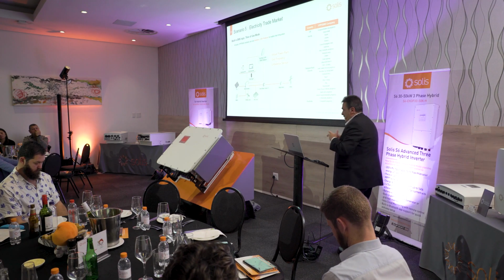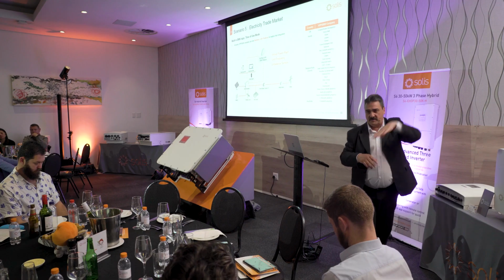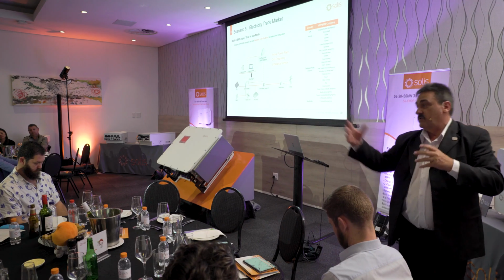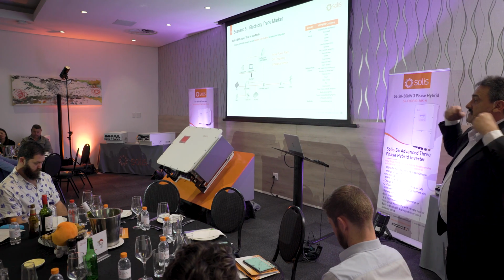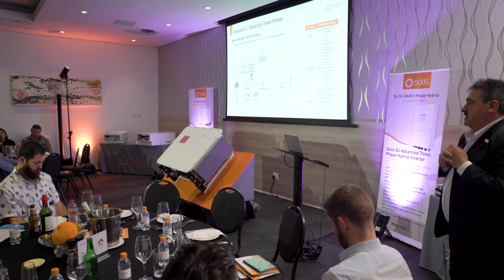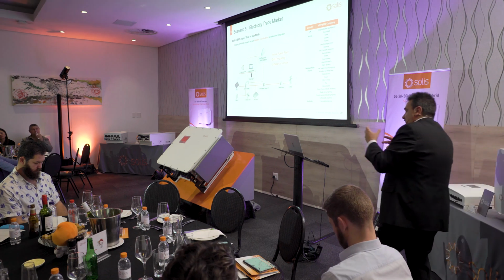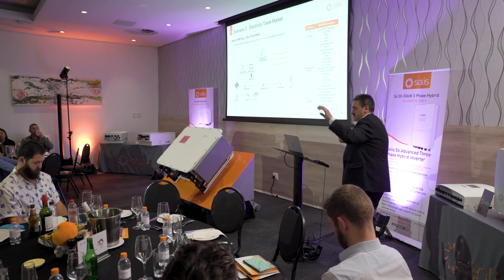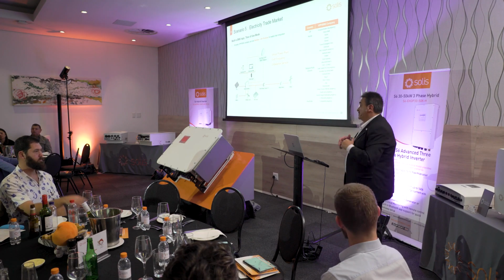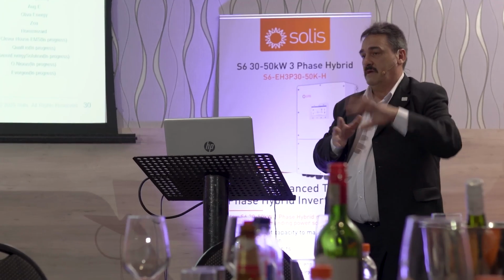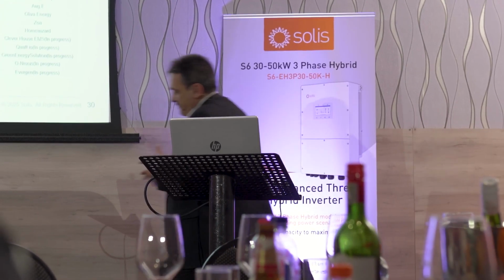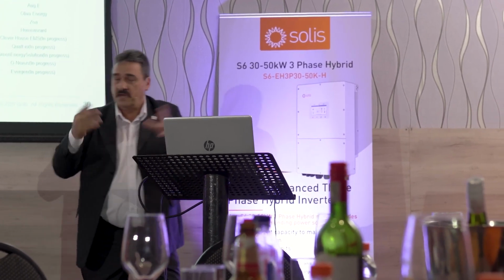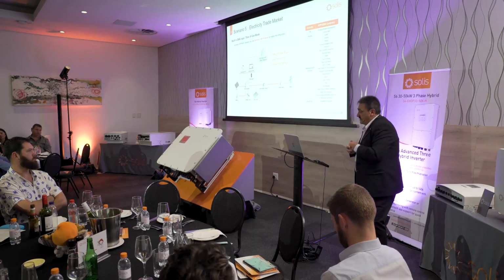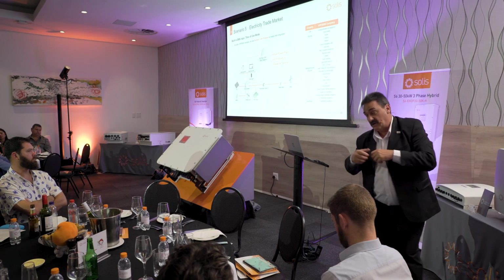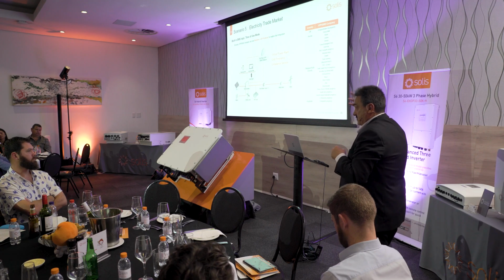It's just on inverter, the council can then say, all right, we've got an overvoltage situation and the grid's a bit unstable. We've got to take some of the injection from the PV systems out of the system, because they do a lot of PV injection. And then they send a signal to the DRM and say, listen, we want all the inverters to slow down to 50%. There are 5 settings: 0, 25, 50, 75, and 100%, and they will control it that way. So the API pretty much does the same thing, but it interfaces and will draw power from the grid, and that will happen automatically if it's integrated properly.